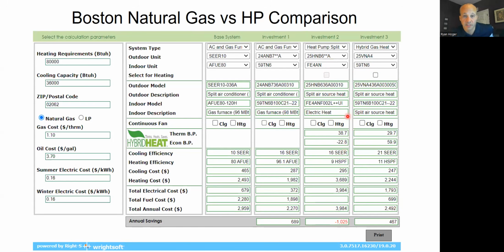But in any case, if I did this all electric system, 38, negative 22, like we said, I switched to the hybrid system, dual fuel. My thermal balance point was 29, meaning that this particular combination of equipment could get me down to 29 degrees on heat pump alone. Economically, it was 60, meaning if it's below 60, it's more expensive to run your heat pump. Don't do it. Run your furnace, dude. And then as we change these numbers, we'll see this guy change. If I make the electric cheaper, then this breakpoint goes down. If I make the gas more expensive, this breakpoint goes down.